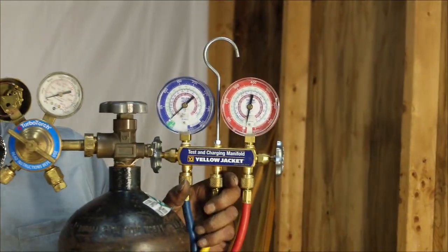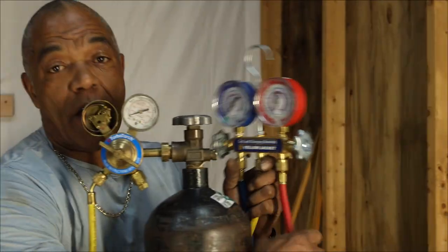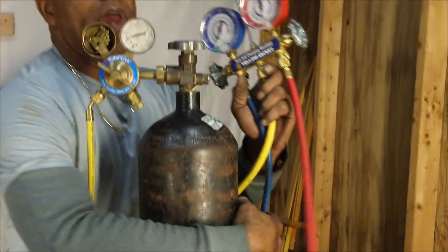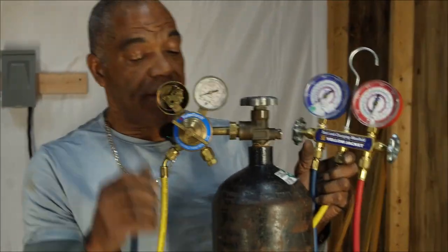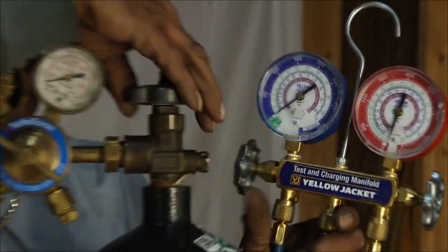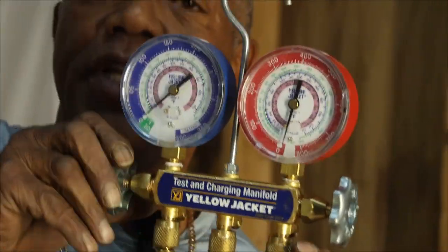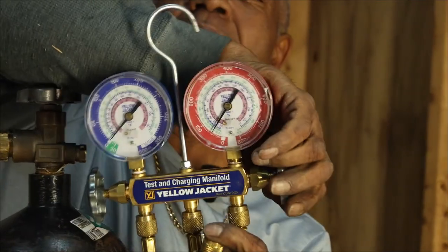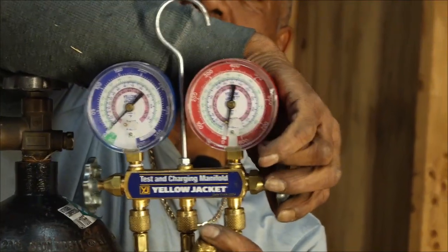But once I hooked my nitrogen up to the system, I would still have my red hooked to the liquid line on the air conditioner and my blue hooked to the suction line. Then when I turn on my gauge, if I open the right one, it'll tell me the level of Freon that I'm putting in the system. You should have seen the gauge move. And my finger can't hold all the pressure that's in the can.